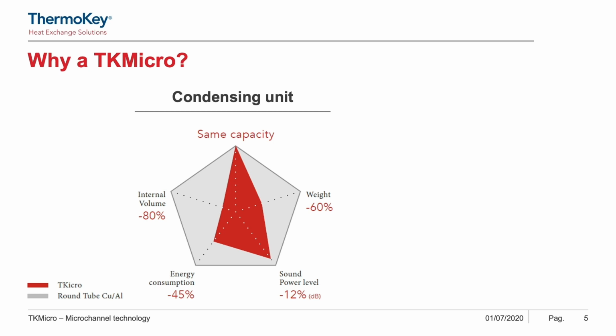Let's consider a condenser for chiller applications and compare microchannel and round tube heat exchangers under the same capacity conditions. Microchannel allow to reduce the refrigerant charge up to 80%. Thanks to lower pressure drop coefficients on the air side, the energy consumption can be cut by 45%, and as a consequence, a lower sound power level can be attained. Aluminium's density is 1/3 of copper's density, and therefore microchannel heat exchangers allow lighter assemblies.